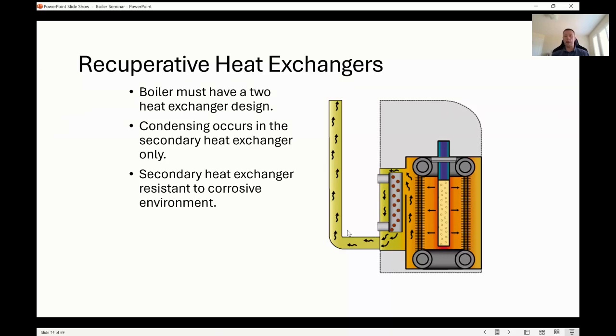You're going to have a primary heat exchanger that does not condense, and in this picture here it's a copper tube heat exchanger, and you're going to have a secondary heat exchanger which is designed to operate in a condensing environment. And that's where all the condensation is going to occur. So with a product like this, the return water is going to go into that secondary heat exchanger first. It's going to be exposed to those flue products, and it's going to have cold temperatures in it. So your flue products are going to condense there.